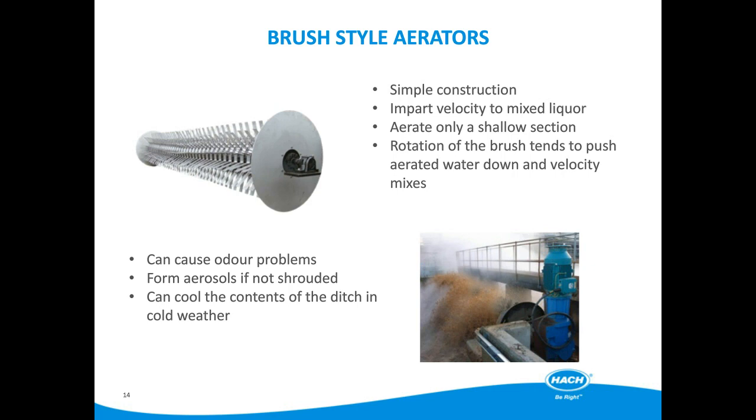All forms of mechanical aerators produce mists or aerosols, which not only promote odour issues, but also cover all equipment within their vicinity with a thin coating of dried sludge, making displays pretty much unreadable. Brush rotors are often covered to reduce this misting, but I'm not able to say if this reduces the efficiency of their operation.